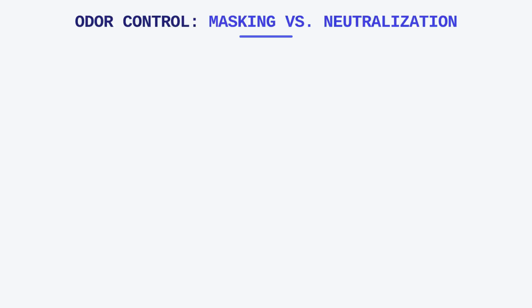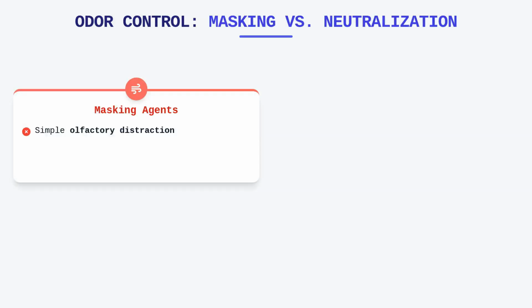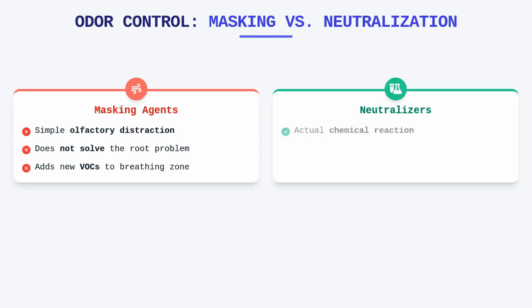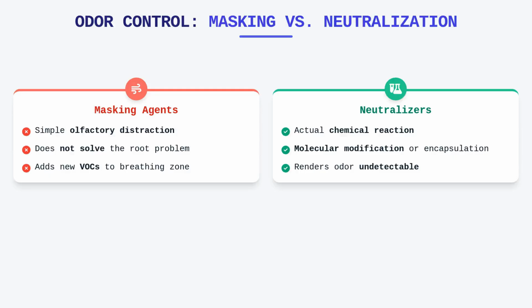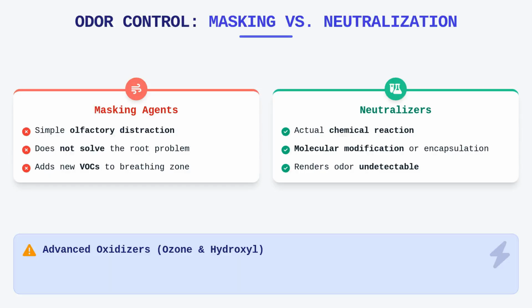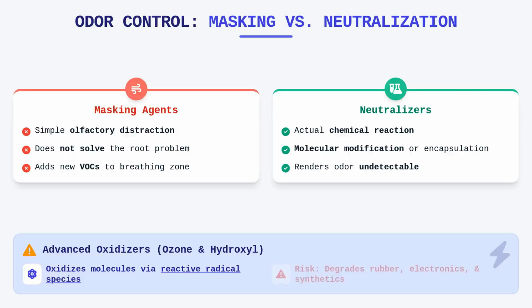When we differentiate between neutralization and masking, we are essentially distinguishing between chemical reaction and simple olfactory distraction. Masking agents, often perfumes, do not solve the problem, but rather introduce a new set of volatile organic compounds into the breathing zone. Conversely, odor neutralizers often work through molecular modification or encapsulation, effectively rendering the odor molecule undetectable or neutralizing its chemical signature. Some systems rely on hydroxyl generators or ozone, which function quite differently by oxidizing odor-causing molecules through the release of reactive radical species. While potent, you must strictly control these technologies to prevent damage to materials or the creation of hazardous indoor environments. Always remember that ozone is highly reactive and can degrade rubber, electronics, and synthetic components within the air handling unit.